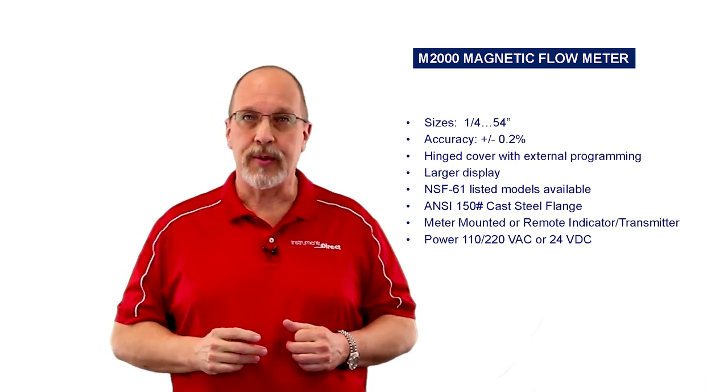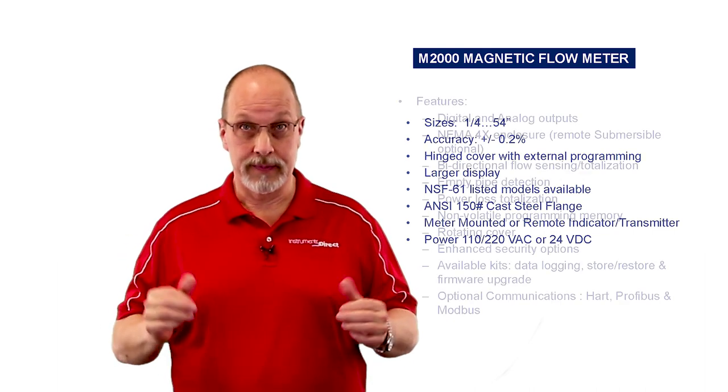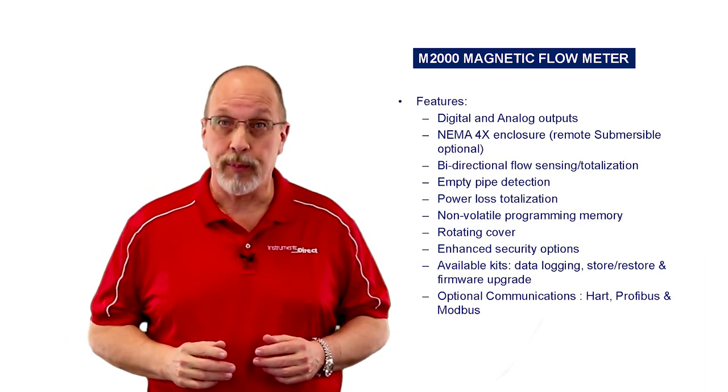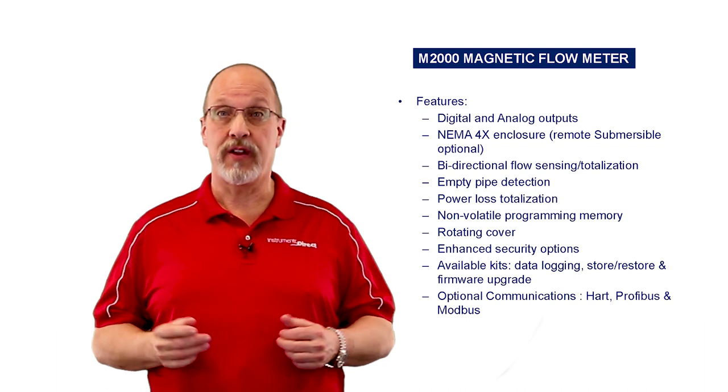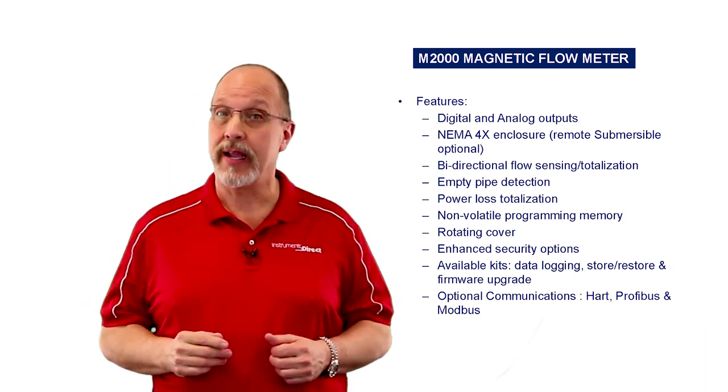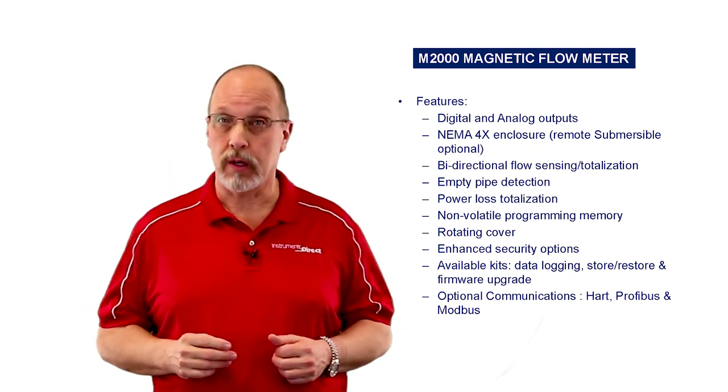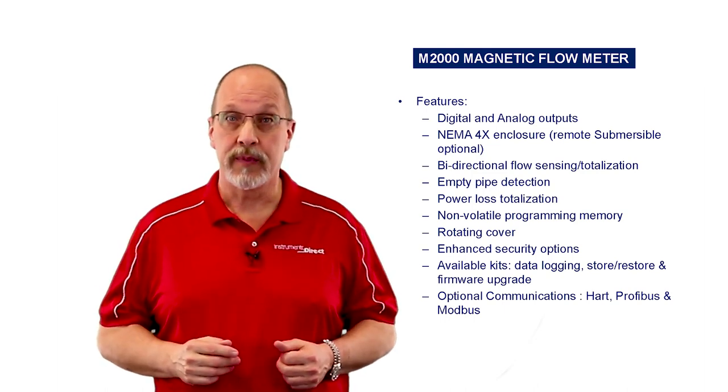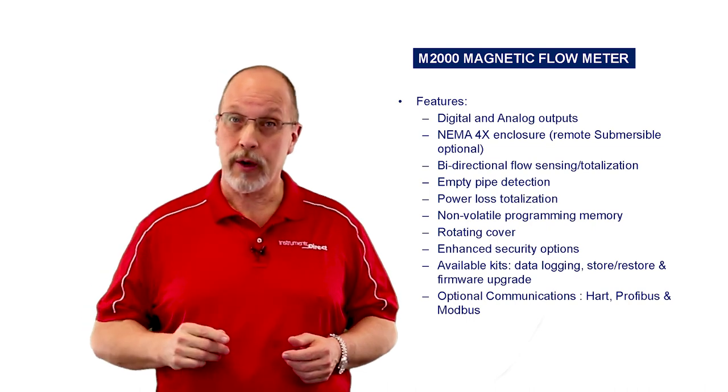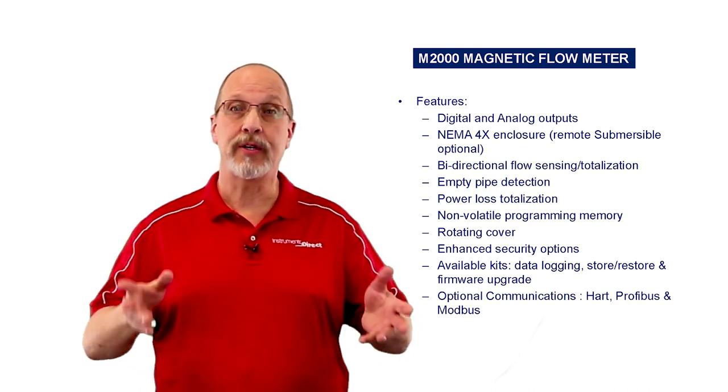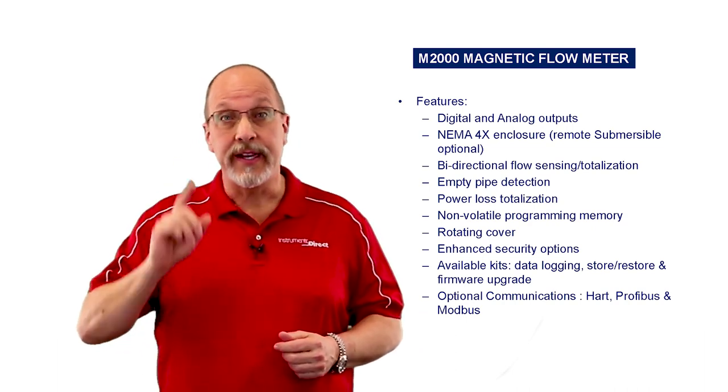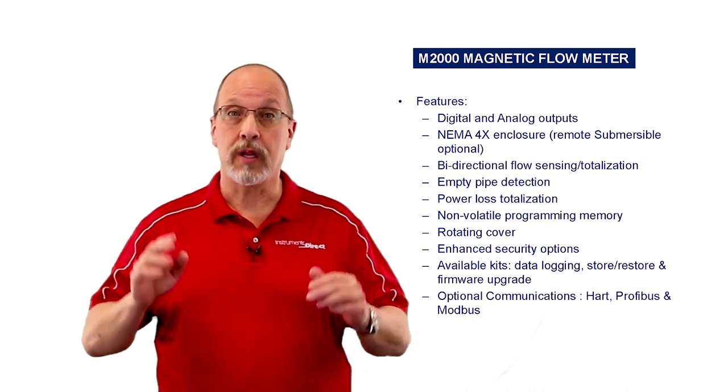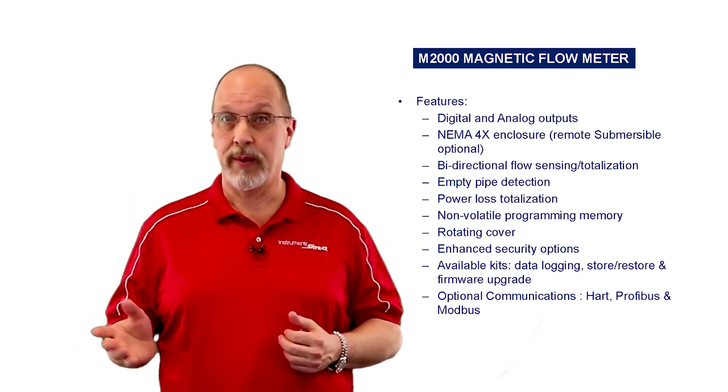Now the power, standard power is 110-220 VAC, or you can get the optional 24-volt VDC. It features digital and analog outputs, NEMA 4X enclosure with optional submersible remote transmitter. It can measure flow bi-directional, it has empty pipe detection, power loss totalization, it has a non-volatile memory, a rotating cover, enhanced security options, and it also offers a few option kits such as data logging, store and restore, and firmware upgrades. In addition, it also has some optional communication features such as HART, PROFIBUS, and MODBUS.